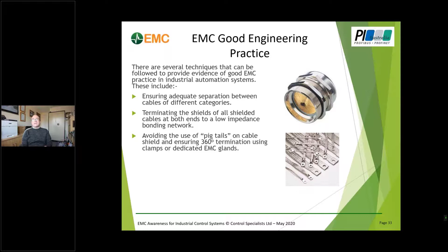But also a low impedance bonding network - I've chosen those words carefully. You avoid the use of pigtails, the idea of taking a shield, twisting it together and putting it into a screw terminal. It's often easier said than done, because very often manufacturers give you a terminal and you're left wondering what you're supposed to do about that. So we'll talk about that shortly.